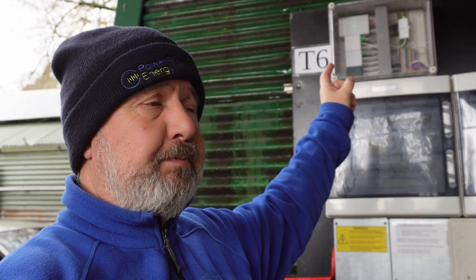The Infinity is basically a little box up here with a green light on it. What it does is it's got some CTs which are measuring the flow and direction of generation and consumption, looking for opportunities to maximise self-consumption. It's also connected to the cloud, so this system can report to the Smappee dashboard and show you whether one of the charging points is available or in use and at what rate. It can also be used with RFID cards to choose who's allowed to use the unit, or with a QR code via the Smappee app to unlock the system.